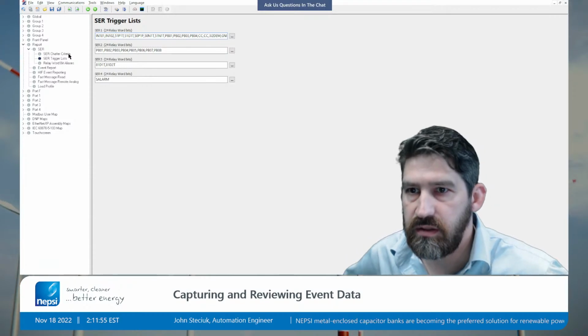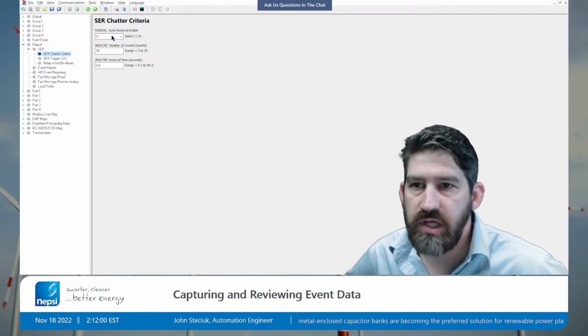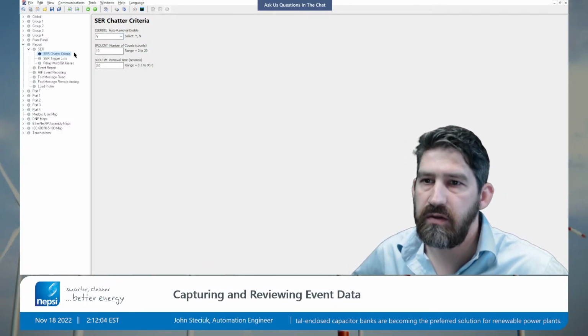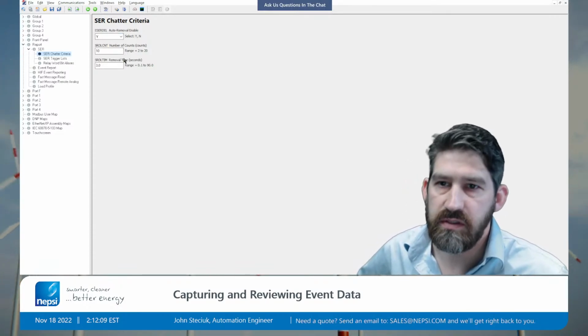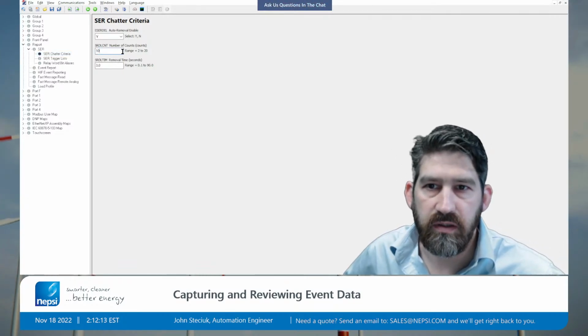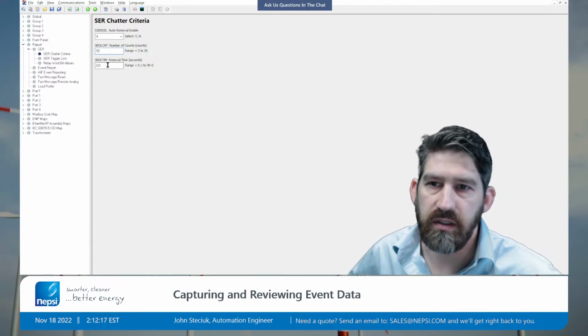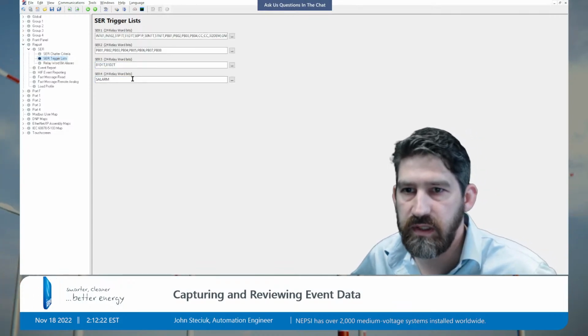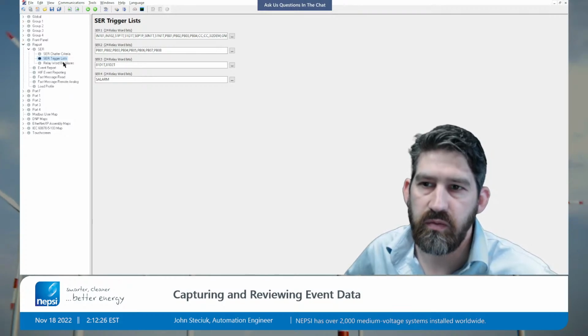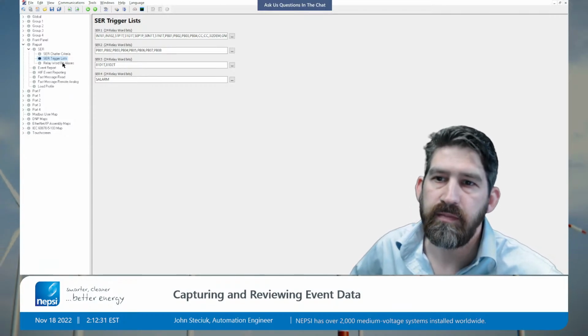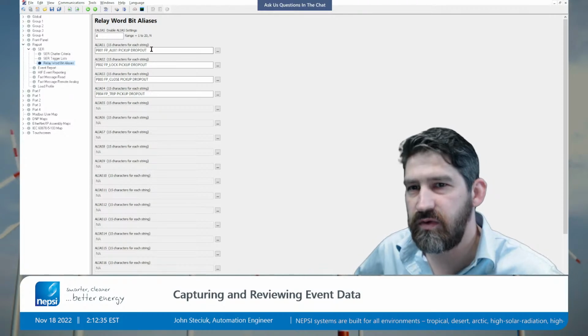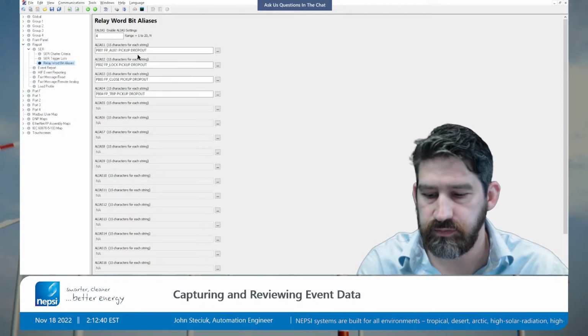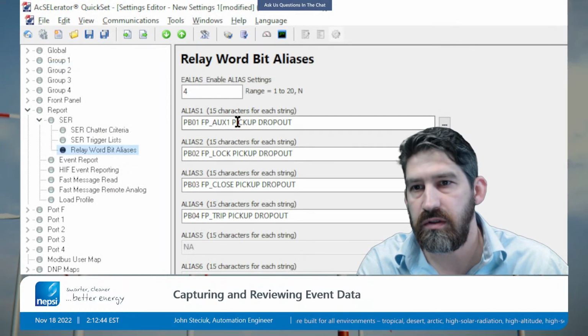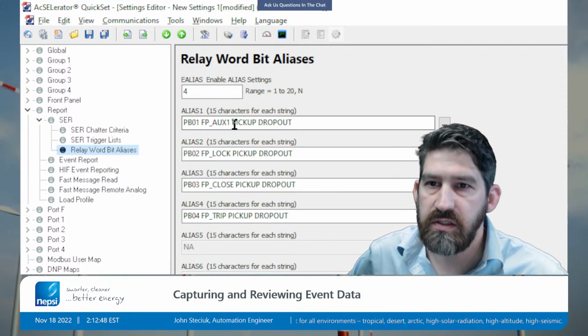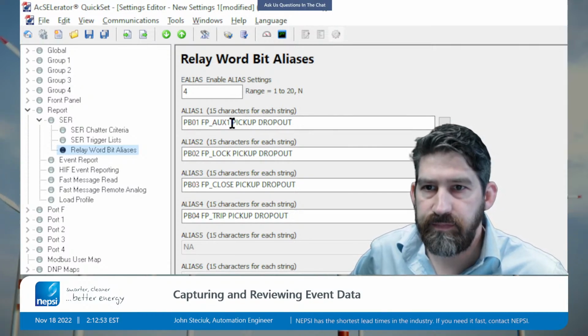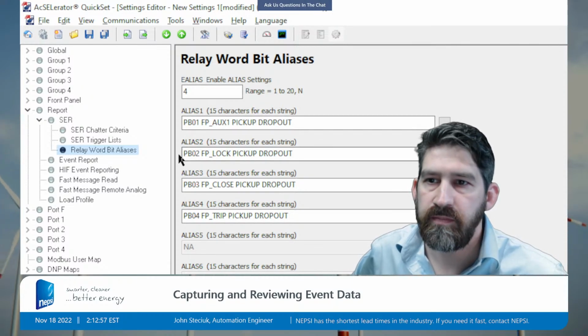The other settings in the SER category are chatter criteria. This allows you to remove a value from the trigger list based on the amount of assertions or deassertions over a certain period of time. So in this example, if a value has changed 10 times within 3 seconds, then it's going to be automatically removed from this trigger list to prevent filling up your log with just that one bit status. And then under aliases, if you don't want to see the SEL relay element names, you can change them here. You specify the relay element and then the alias that you want to use, and then what you want the message to be on assertion and then on deassertion. So you can customize it a bit there.